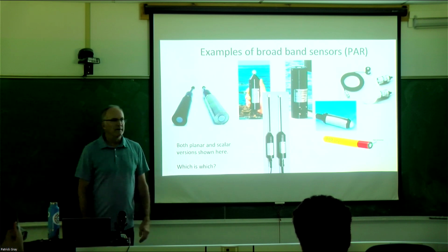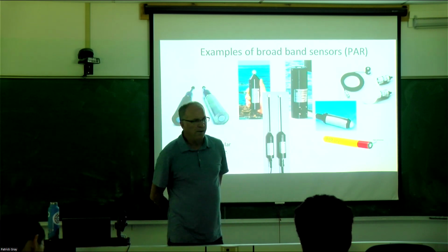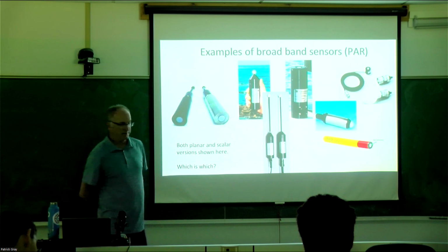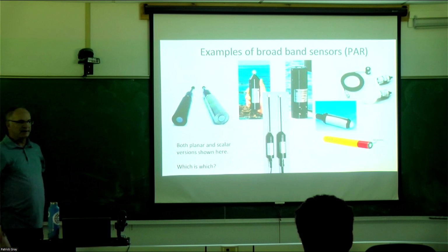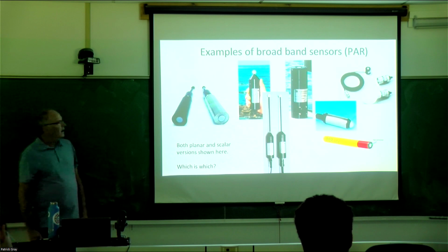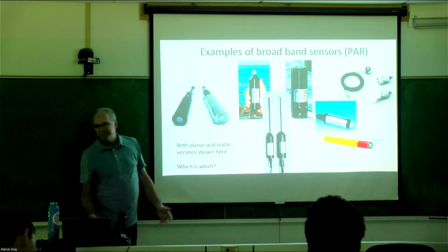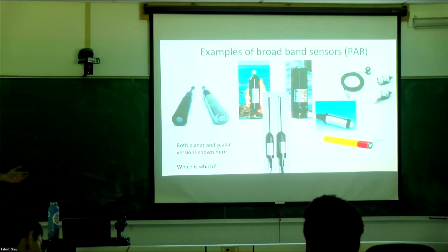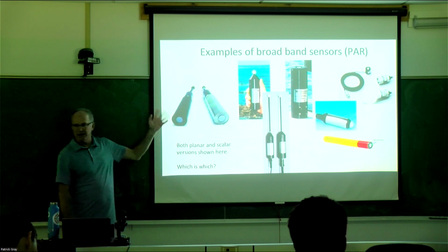Does the scalar return a measurement for all angles? No, just one measurement. It's an integrated measurement over all those solid angles. So why would you want a planar over a scalar? Various different reasons. These aren't easy to make. They're not as easy to keep from active biofouling. Here you can use paddles, shutters, wipers, things like that.